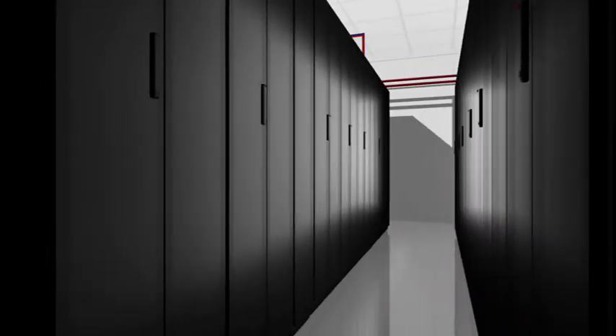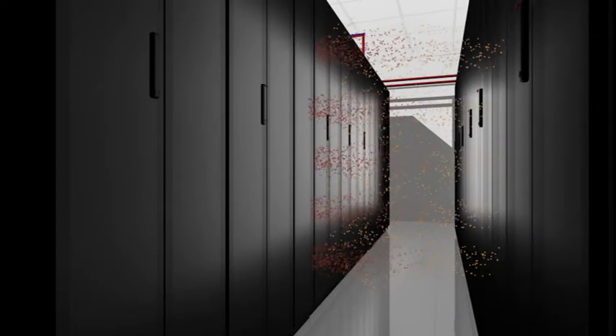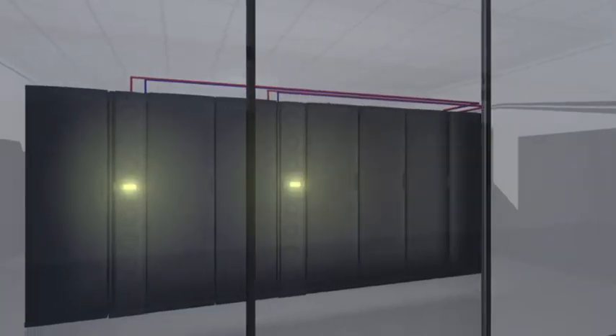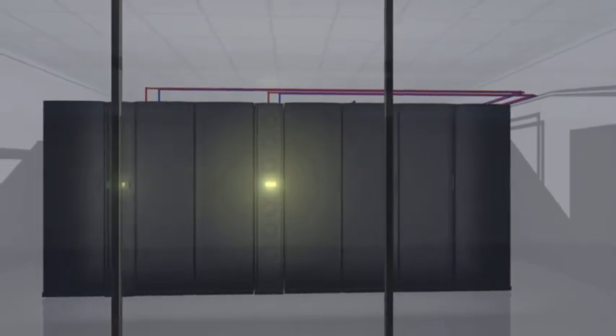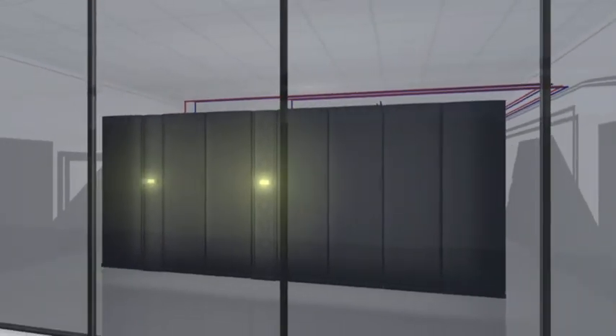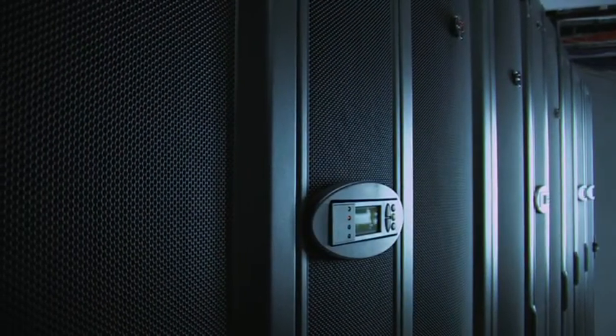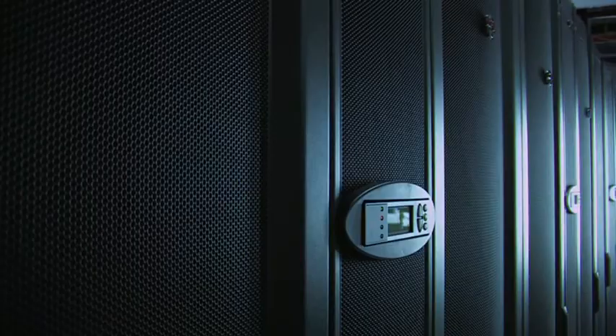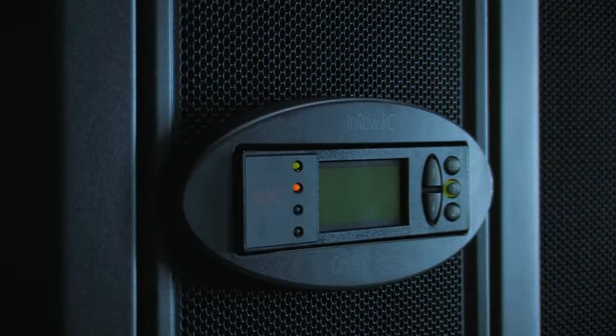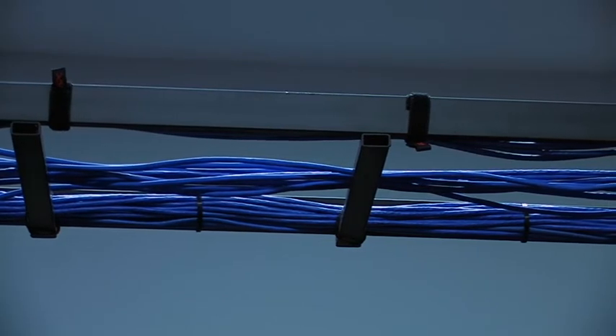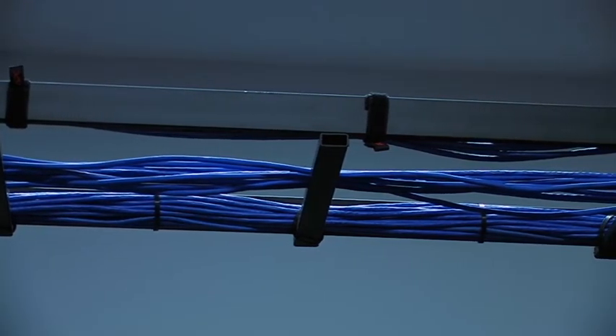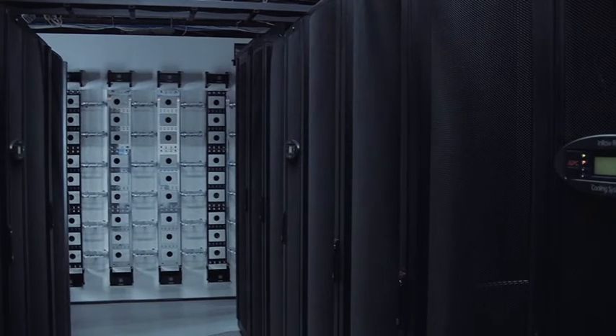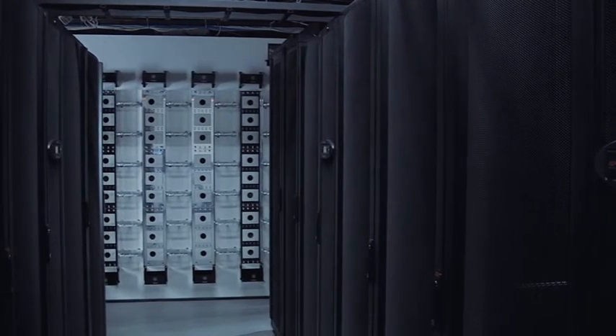The cooling units are installed between the racks and have now been configured for a medium density environment. However, the design allows for a simple and easy expansion of the system for densities up to 20 kilowatts per rack. The in-row cooling units extract heat from the hot aisle and deliver cold air in the cold aisle. Power and data cables are installed overhead, so a raised floor wasn't needed for cold air distribution or cabling.